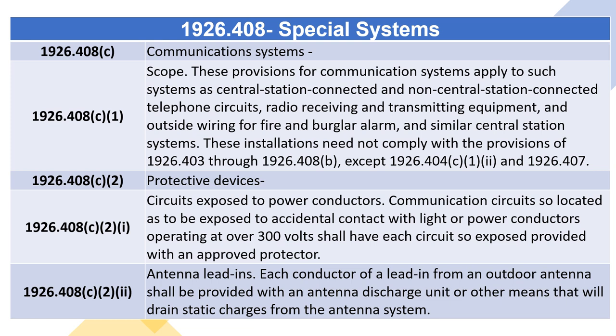1926.408(C)(2) — Protective Devices. 1926.408(C)(2)(i) — Circuits Exposed to Power Conductors. Communication circuits so located as to be exposed to accidental contact with light or power conductors operating at over 300 volts shall have each circuit so exposed provided with an approved protector. 1926.408(C)(2)(ii) — Antenna Lead-Ins. Each conductor of a lead-in from an outdoor antenna shall be provided with an antenna discharge unit or other means that will drain static charges from the antenna system.